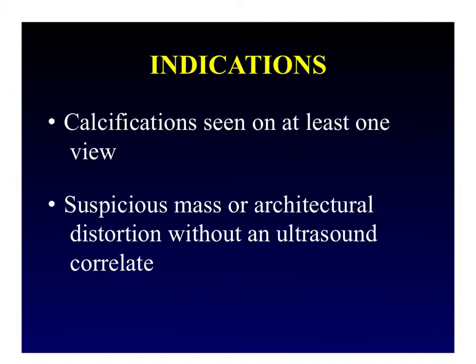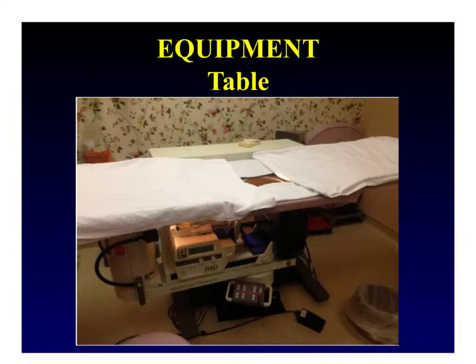Now it's time to review the equipment, starting with the table. At our institution we use the Hologic-Lorad MultiCare Platinum Table. The woman will lay prone on the table and the targeted breast will hang down through the hole. The orientation of the patient on the table will depend on the breast that is targeted and the approach. When we start the biopsy, the biopsy table will move up and all of the action will happen below.